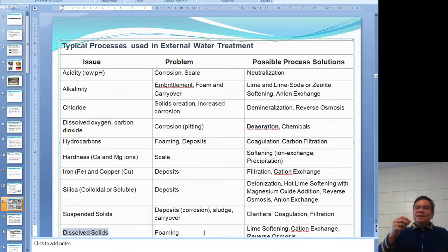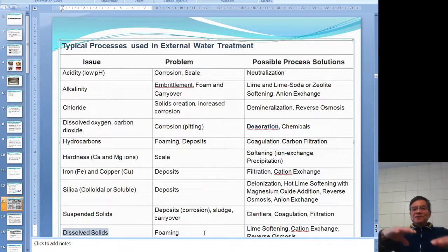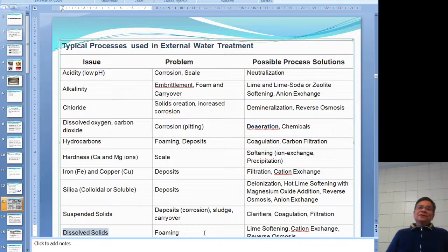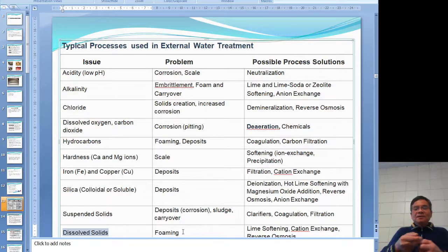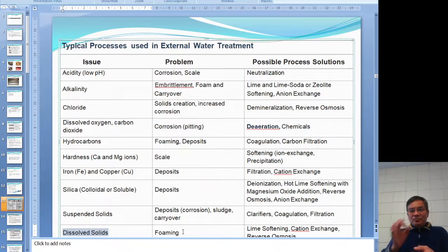As dissolved solids in the boiler water increase, you will have foaming. Foaming gives a false reading on your water glass or level transmitter. Your boiler may actually be very low on water, but because of foaming, the sensor reads a high enough level, so you stop adding feed water. Eventually your boiler will trip. Another effect of foaming is that it promotes carry over, which carries minerals to the turbine blades and ruins the turbine.